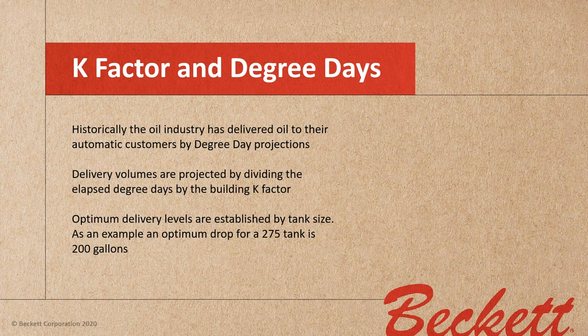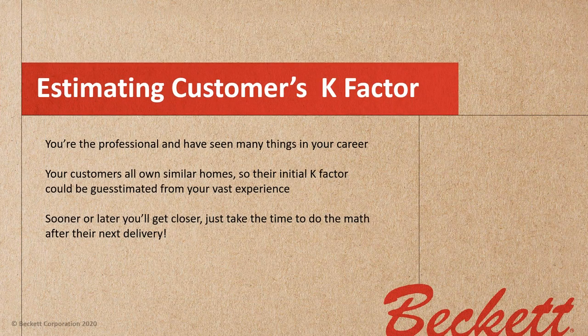Historically, the oil industry has delivered fuel oil to automatic customers by degree day projections. Delivery volumes are projected by dividing the elapsed degree days by the building K-factor. Optimum delivery levels are established by the tank size. For my example this afternoon, I'm going to assume we all have 275-gallon tanks and that the optimum drop is going to be 200 gallons. Throughout the rest of my presentation, that's the example I'm going to use.